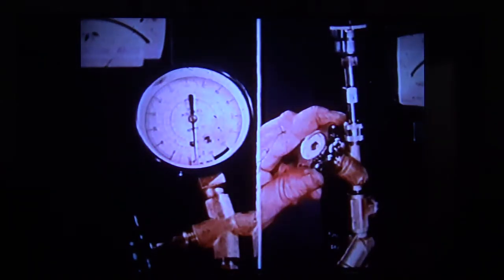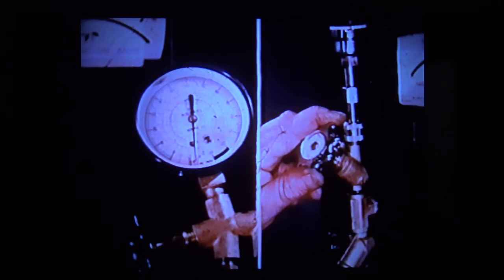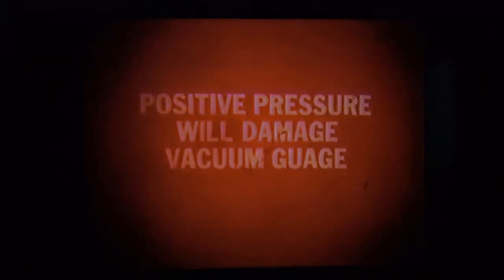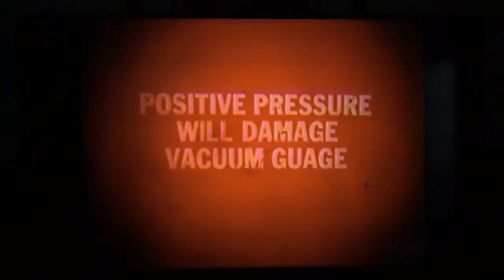After the suction gauge on the manifold shows that the system is in a vacuum, open the vacuum gauge control valve on the service station and continue to operate the vacuum pump for 10 minutes. Caution, do not apply positive pressure to the system when the vacuum gauge control valve is open, or damage to the vacuum gauge tube will result.